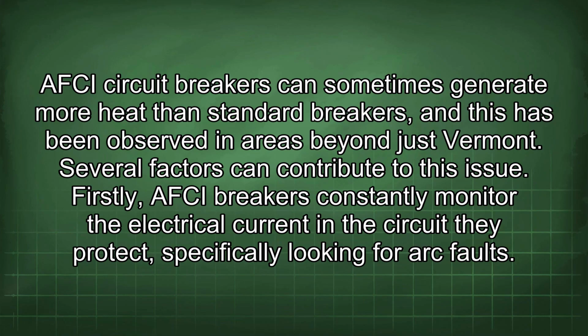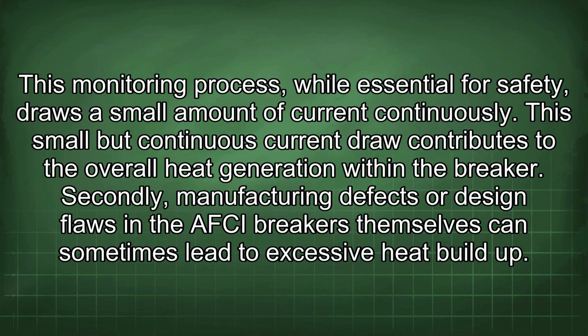AFCI circuit breakers can sometimes generate more heat than standard breakers, and this has been observed in areas beyond just Vermont. Several factors can contribute to this issue. Firstly, AFCI breakers constantly monitor the electrical current in the circuit they protect, specifically looking for arc faults. This monitoring process, while essential for safety, draws a small amount of current continuously. This small but continuous current draw contributes to the overall heat generation within the breaker.